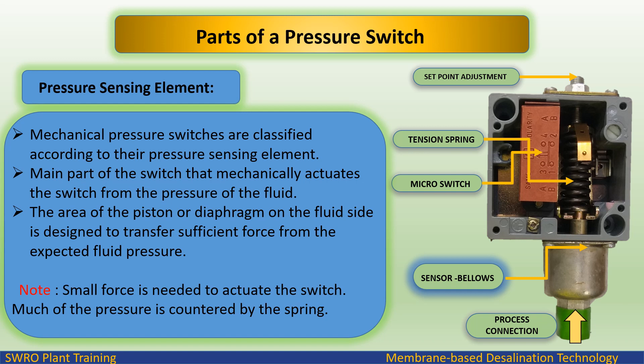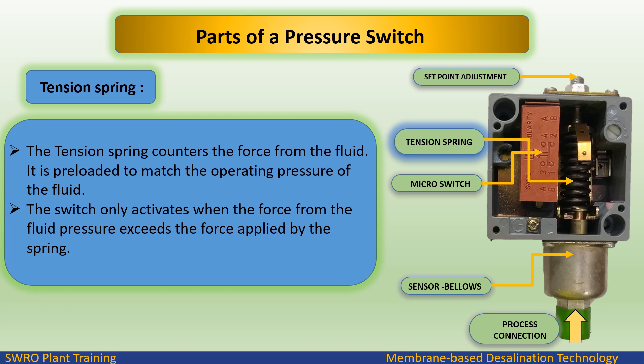Pressure sensing element. Mechanical pressure switches are classified according to their pressure sensing element. It is the main part of the switch that mechanically actuates the switch from the pressure of the fluid. The area of the piston or diaphragm on the fluid side is designed to transfer sufficient force from the expected fluid pressure. Note: only a small force is needed to actuate the switch; much of the pressure is countered by the spring. The tension spring counters the force from the fluid and is preloaded to match the operating pressure. The switch only activates when the force from the fluid pressure exceeds the force applied by the spring.